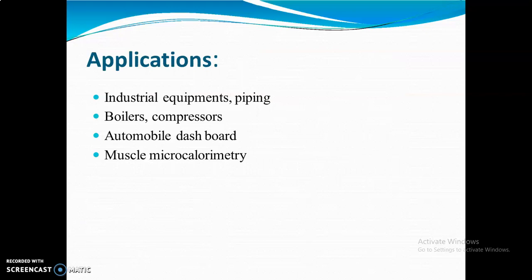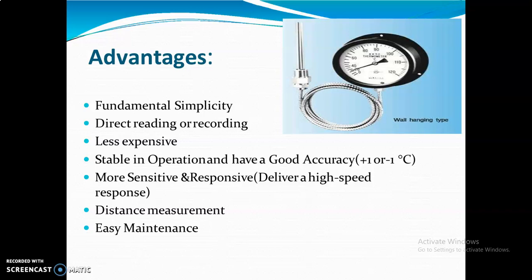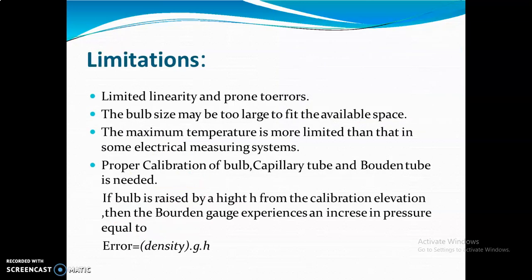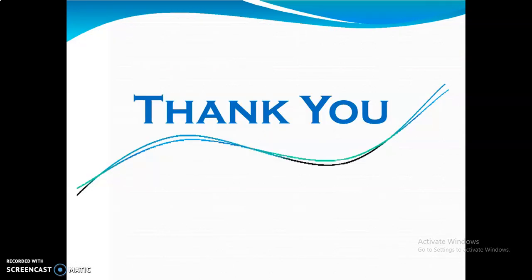Applications include use in boilers, compressors, automobile dashboards, and industrial equipment piping. Advantages include: it is very simple, offers direct reading or recording, is less expensive, allows distance measurement, and is more sensitive with easy maintenance. Limitations include limited linearity, bulb sizes may be too large to fit available space, proper calibration is required, and if the bulb rises in height from the calibration elevation, the Bourdon gauge experiences increasing pressure equal to the error rho·g·h.